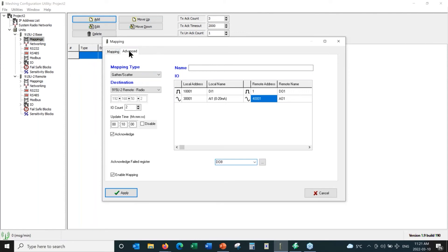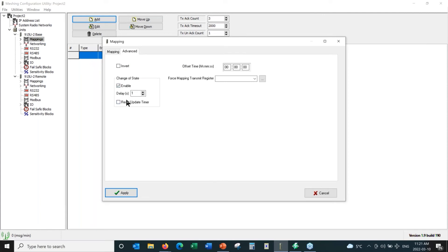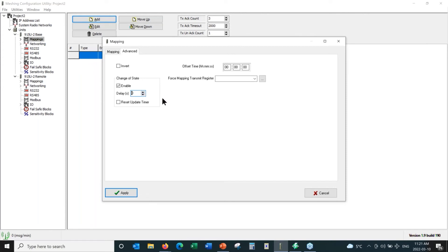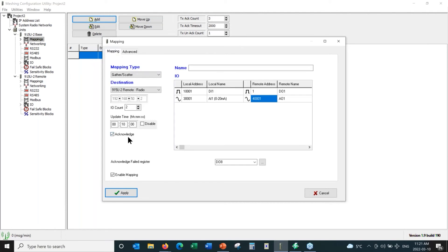I'm going to head over to Advanced. There's a built-in delay of one second — I'm going to drop that to zero. This delay ensures that if we have noise, the radio won't transmit a noise value. With it set to one second, the input has to stabilize at its final value for a minimum of one second before transmitting. These radios monitor for change of state, which is why the update time is set to a fairly long time frame — like 10 minutes normally. I'm going to change this to five seconds so we don't have to wait long for transmissions during this demo.